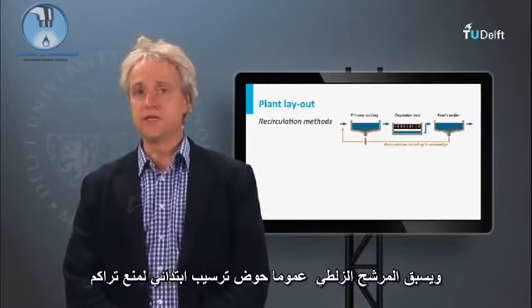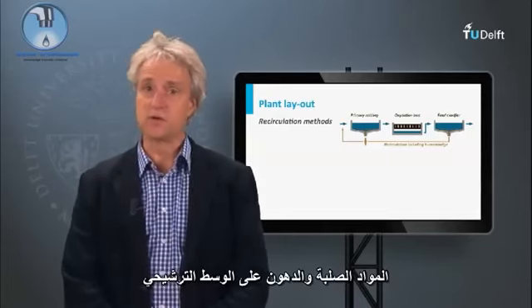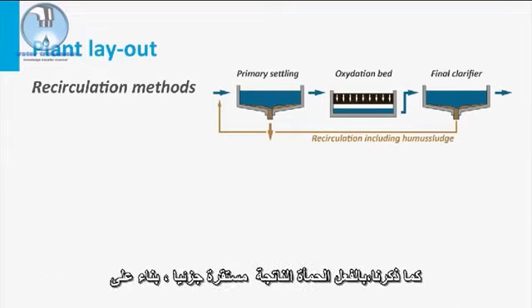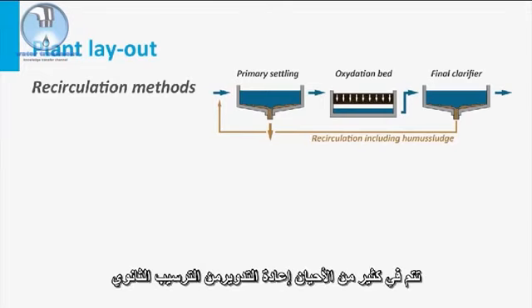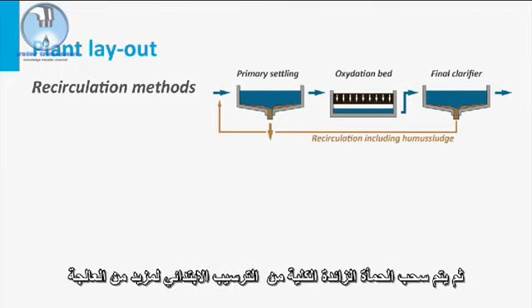A trickling filter is generally preceded by a primary clarifier to prevent the accumulation of solids and fats onto the filter bed. Excess sludge leaves the filter with the effluent and is retained in a secondary clarifier. As mentioned, the produced sludge is already partly stabilized, dependent on the applied BOD loading rate. From the secondary clarifier, often recycling is performed by pumping the secondary sludge with the nitrified effluent to the primary clarifier. The overall excess sludge is then withdrawn from the primary clarifier for further treatment.